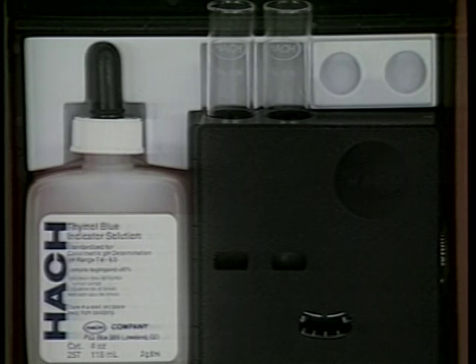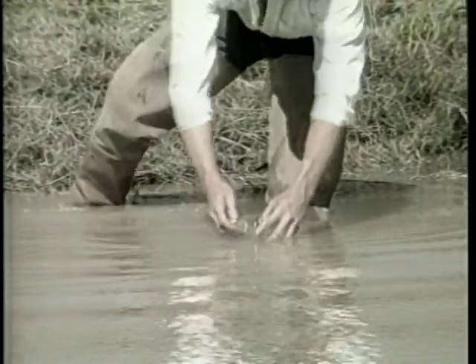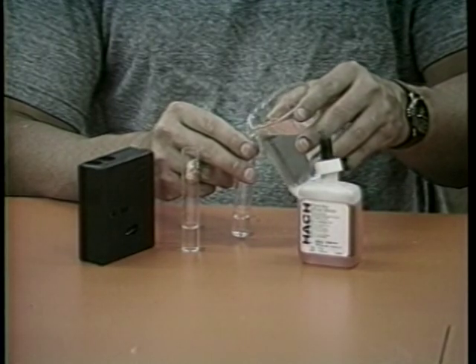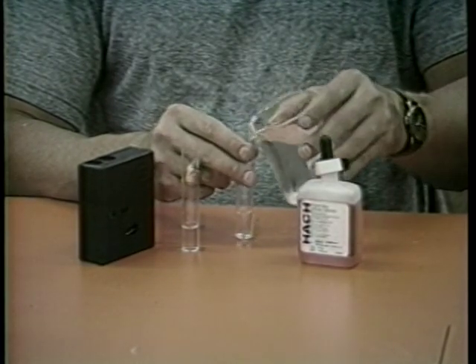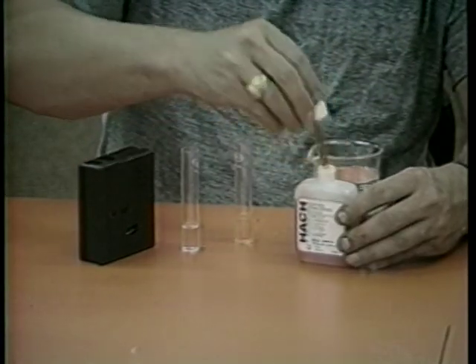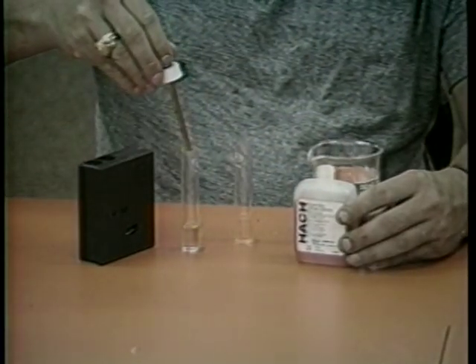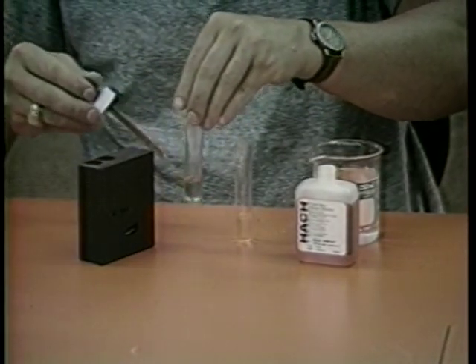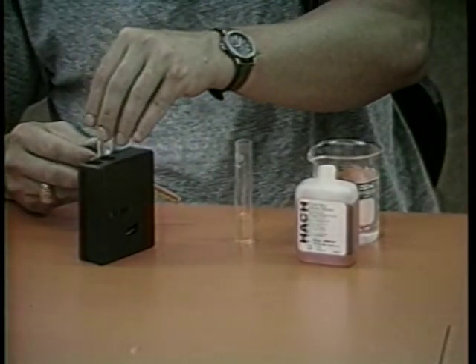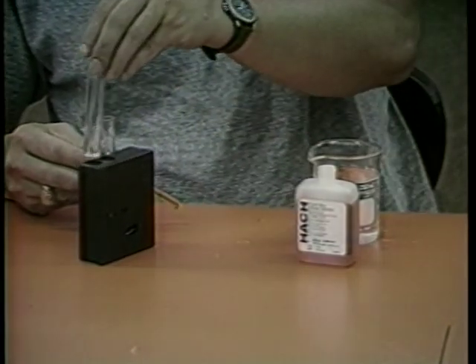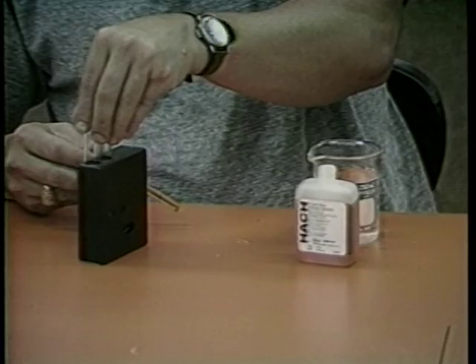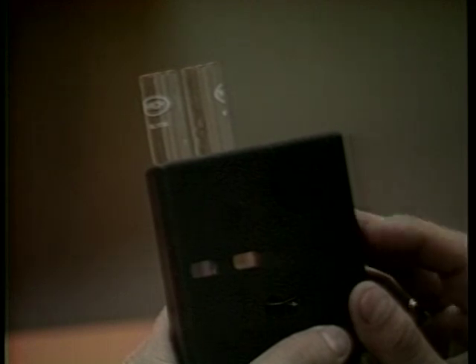To test the pH using the narrow range method, proceed as follows. Obtain a water sample as described for the wide range test. Fill the two viewing tubes to the 5 mL mark with the sample. Add 6 drops of the thymol blue indicator solution to one of the tubes and swirl to mix. Insert this tube into the opening on the right side of the color comparator. Insert the other tube into the left opening. Hold the comparator up to the light source and rotate the disc to obtain a color match. Read the pH from the wheel.